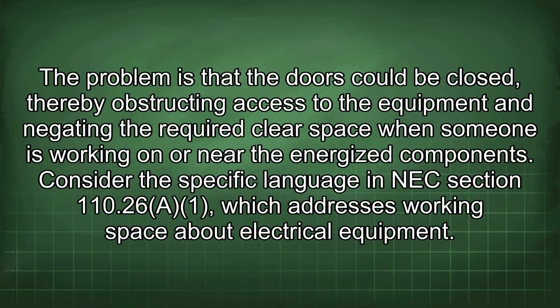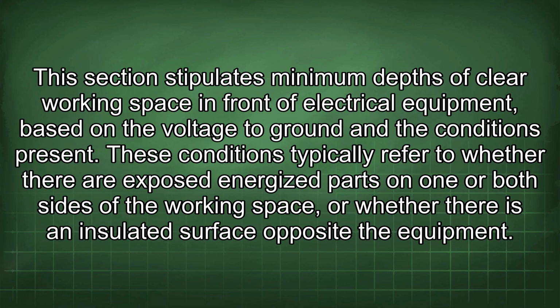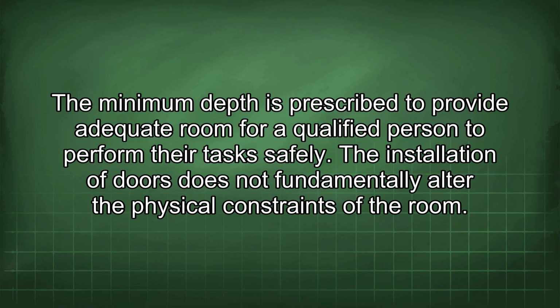The problem is that the doors could be closed, thereby obstructing access to the equipment and negating the required clear space when someone is working on or near the energized components. Consider the specific language in NEC section 110.26(A), which addresses working space about electrical equipment. This section stipulates minimum depths of clear working space in front of electrical equipment, based on the voltage to ground and the conditions present. These conditions typically refer to whether there are exposed energized parts on one or both sides of the working space, or whether there is an insulated surface opposite the equipment. The minimum depth is prescribed to provide adequate room for a qualified person to perform their tasks safely.